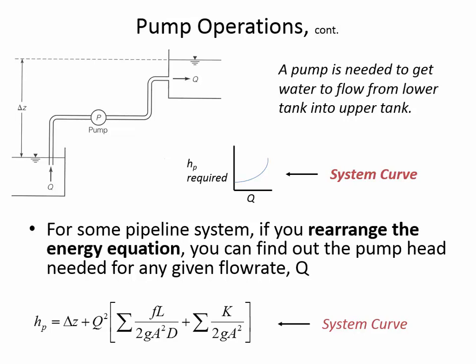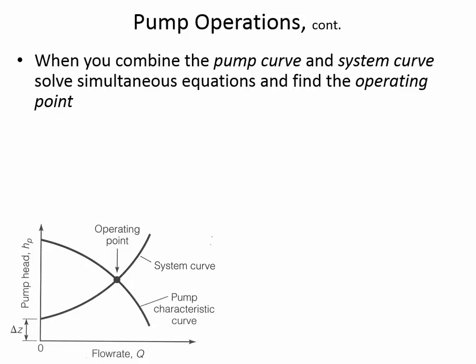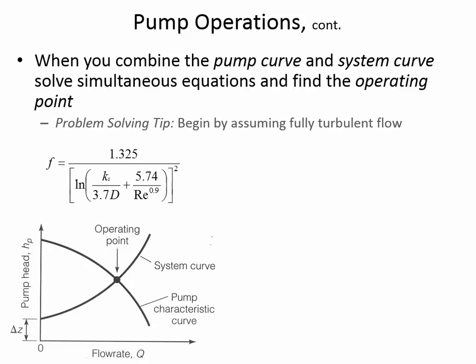So to solve systems, to find out what the actual operational flow rate is going to be, the operating point is where the pump curve and the system curve intersect. And so graphically, that's what it looks like for them to intersect. But you can set the two equations equal to each other, and you can solve for Q. That'll be the only unknown if you have HP equal to HP, where on one side of the equation is the system curve, on the other side of the equation is the pump curve.